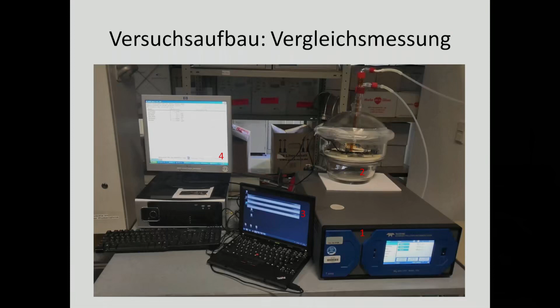And it showed during several days, which are these clouds of points here, that NO2 had some influence on the measuring value. I chose some values where the temperature was only within a very small range, and the moisture was also in a small range of values, and the NOx concentration was also within the same region. So even during several days, you get this calibration function, and if you correct the values for temperature from the function that I've measured before, it looks a little bit better, but it shows a big problem here.